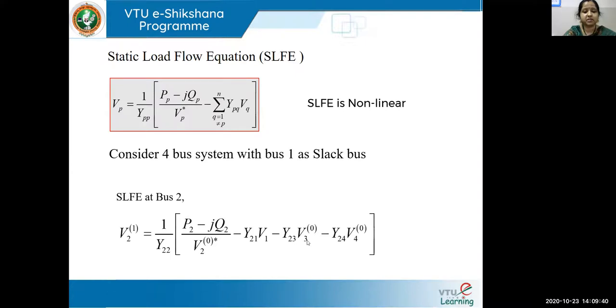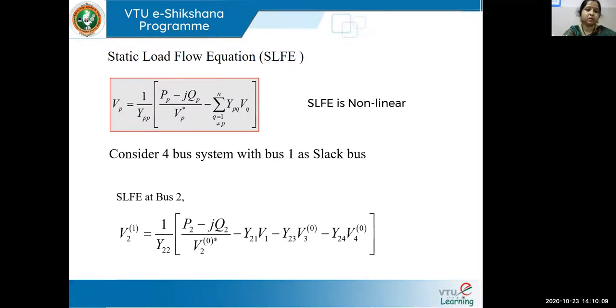The initial voltages at all PQ buses will be assumed close to the actual value. Usually we assume these voltages as 1 + j0, which we call the flat voltage profile. To repeat: all initial values of PQ bus voltages are considered as 1 + j0, which is called the flat voltage profile.